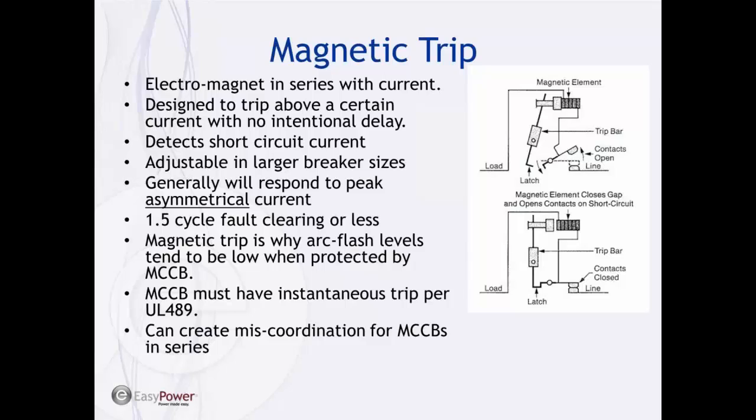In the larger molded case breakers, this is going to be adjustable, and the smaller ones, such as you might have in your house, it's non-adjustable. And the instantaneous pickup is defined as a multiple of the current rating, defined in the UL 489.